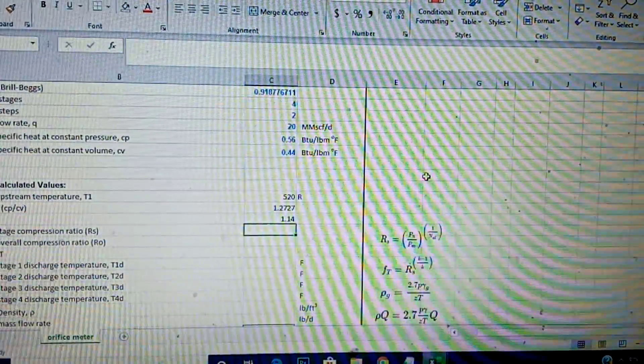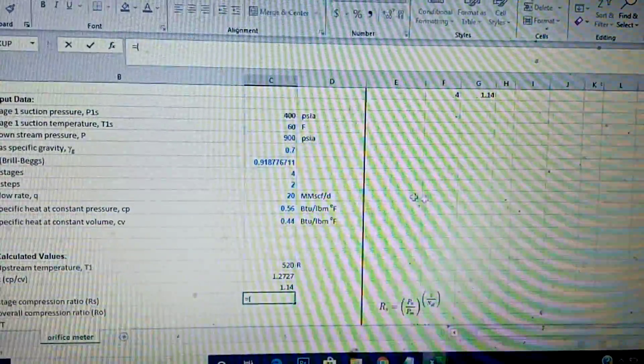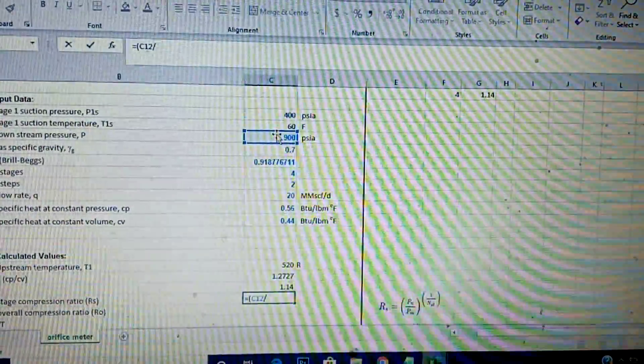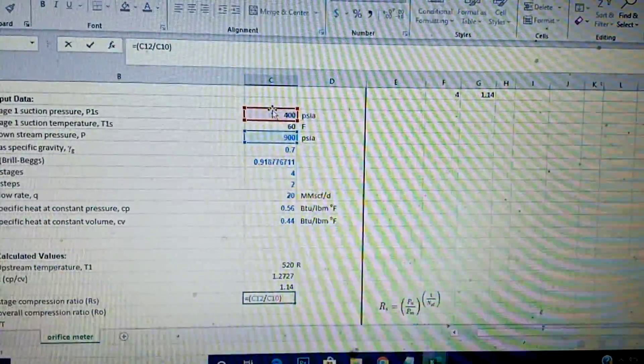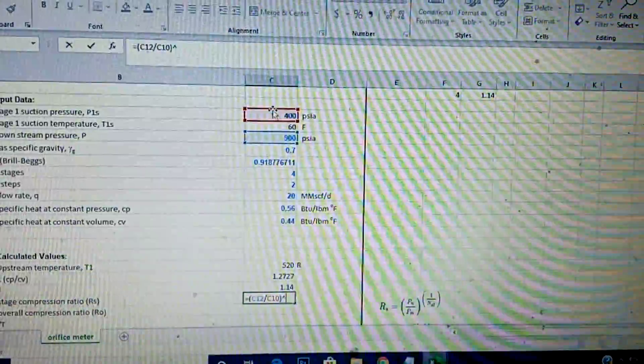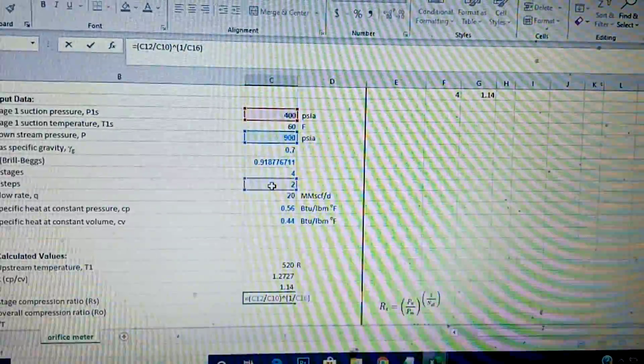Now the stage compression ratio equals the downstream pressure over the upstream pressure, raised to the power of one over the number of steps — which is (900/400)^(1/2). That gives a stage compression ratio of 1.5.